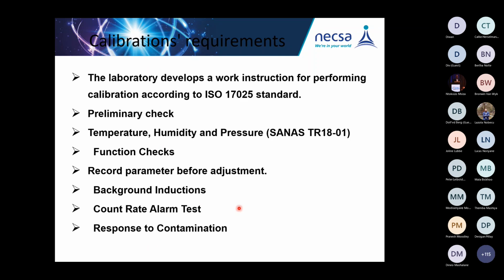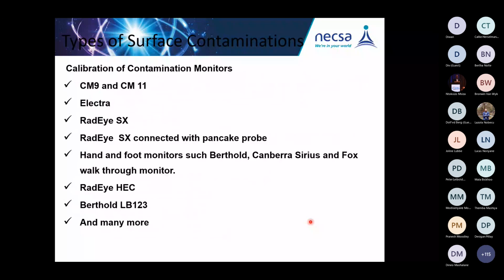Count rate alarm test, and then you also test whether the instrument still triggers the alarm when there is excessive radiation and responds to contamination. Those are for instruments which have that functionality, not for all the instruments.